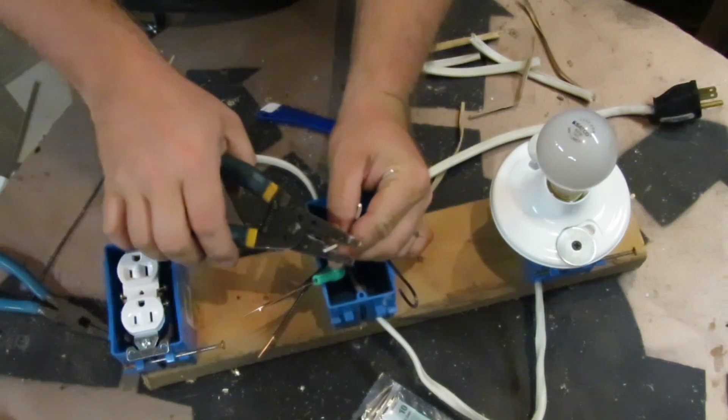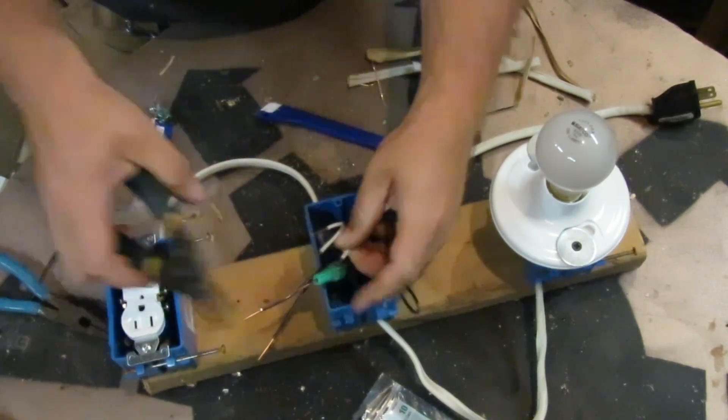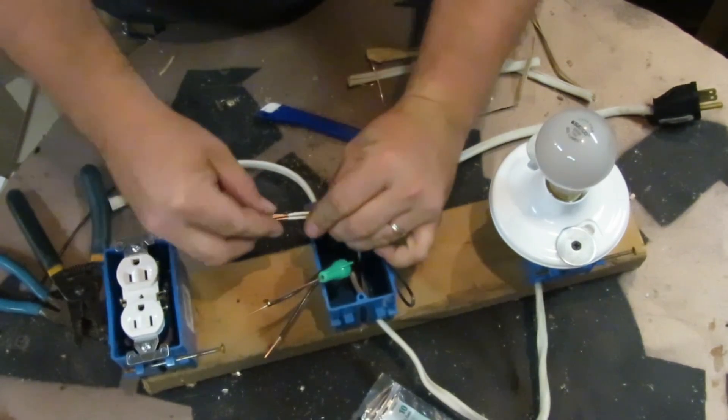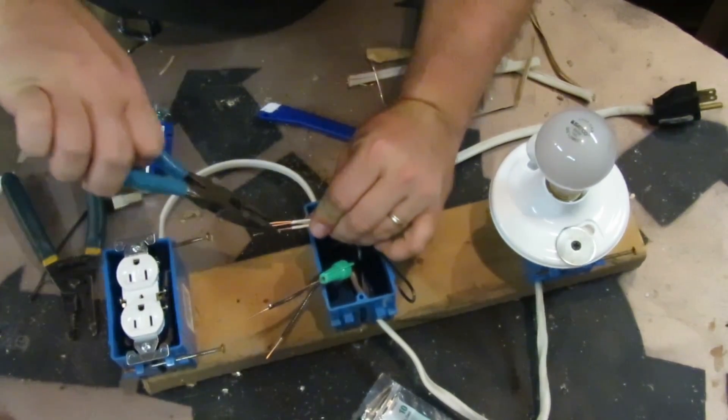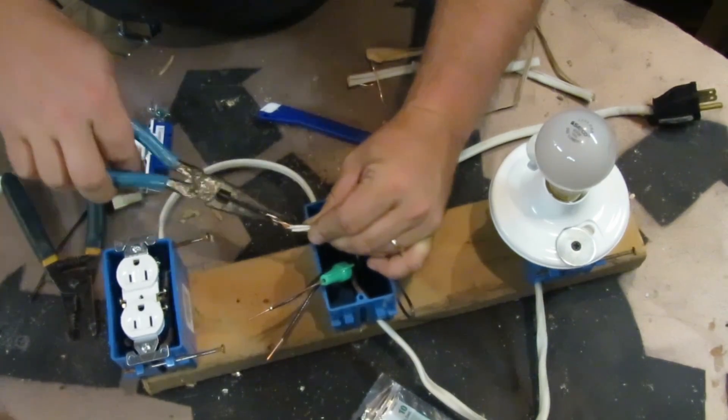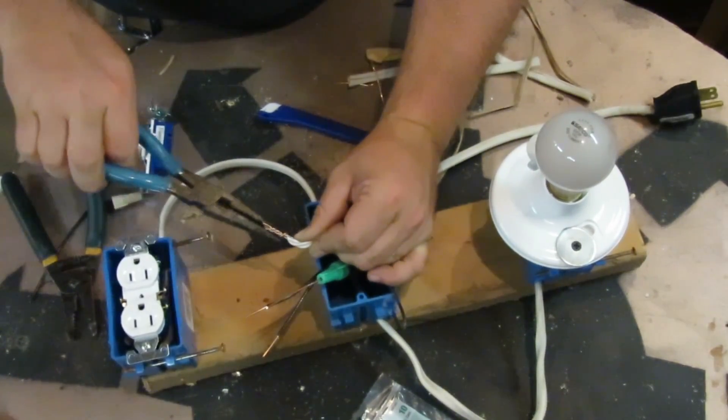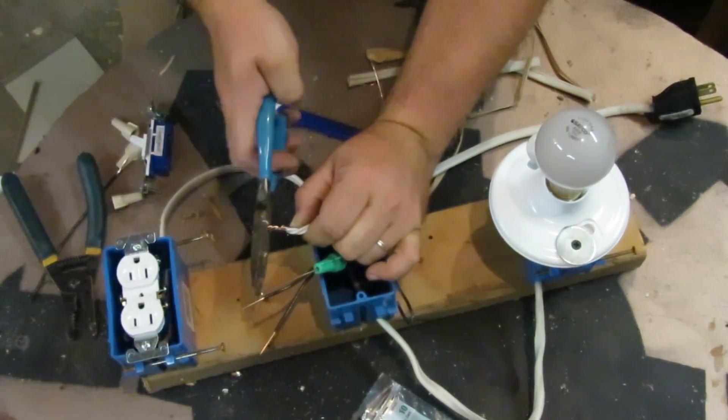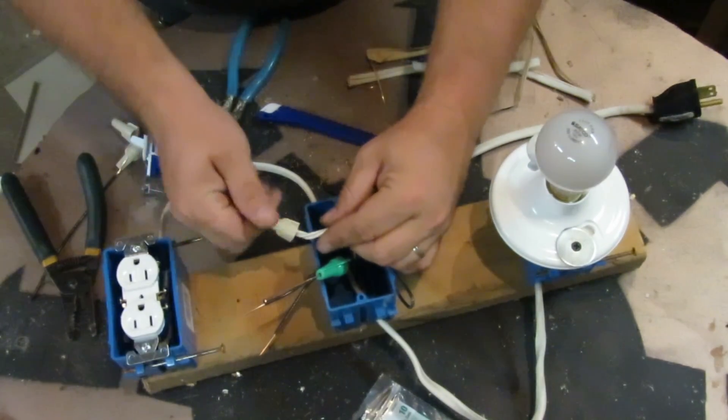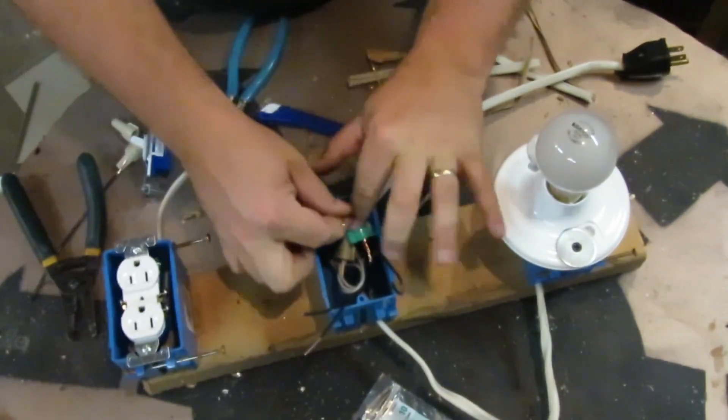You just want to strip your neutrals off and then twist the copper together. Just get a nice twist on it and trim off the ends. Then you just take a regular wire nut and twist that on. Then you just want to stuff all this into the box.